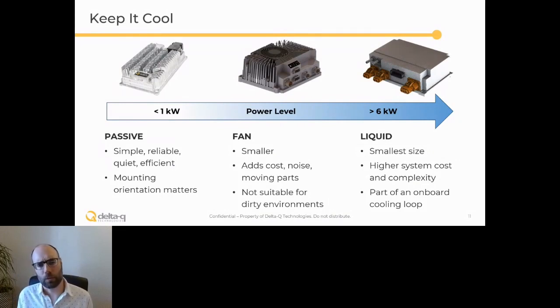Somewhere around 6 kilowatts or so, and this really depends on the application, there is definitely a break point where you start looking at liquid cooling. This has the smallest size, so you can get the highest cooling performance and the highest power density, but it greatly adds to the cost and complexity of the system.